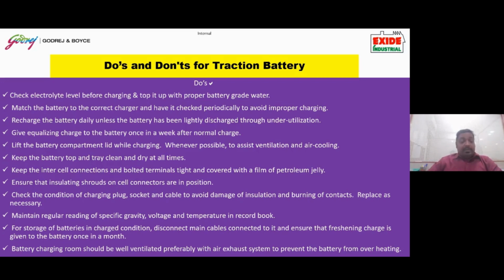Intercell connectors, and especially for the bolt-on batteries, please check the bolt-on connector tightness periodically, and ensure that the insulating shrouds on the cell connectors are in position, because if these are not in position, then any external object falling on the battery might short the positive and negative plate and cause an explosion.